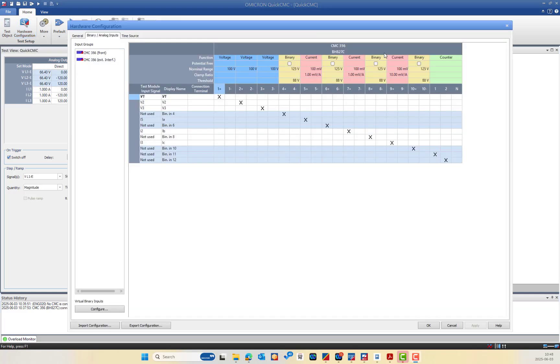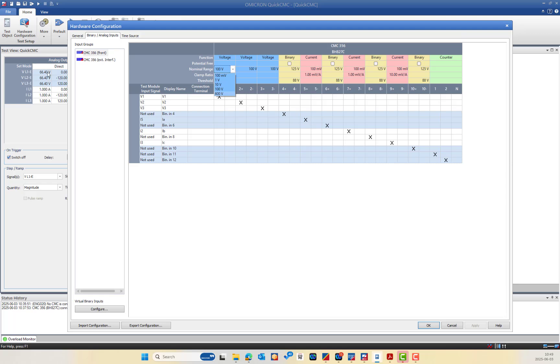Here is the hardware configuration as explained. The first three inputs are configured to measure the voltage directly up to 100V. Make sure to choose the nominal range to be higher than the expected measurement value. For example, if measuring 66V, the smallest range higher than that is 100V. The same applies for channel 2 and channel 3.